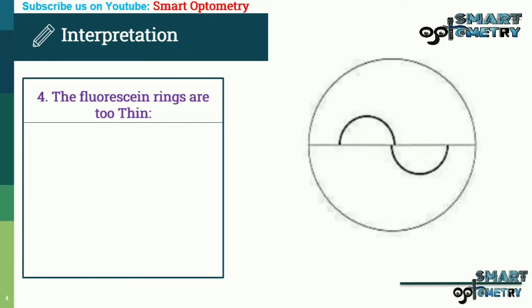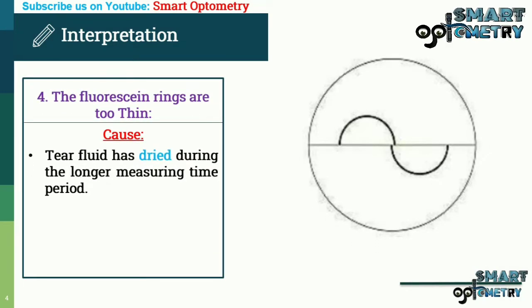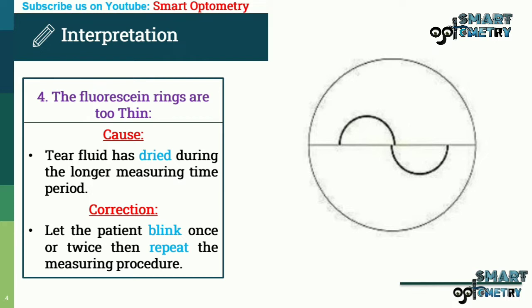Fluorescein rings are too thin. This is because the tear fluid has dried during the longer measuring time period. The correction is to let the patient blink once or twice, then repeat the measuring procedure.